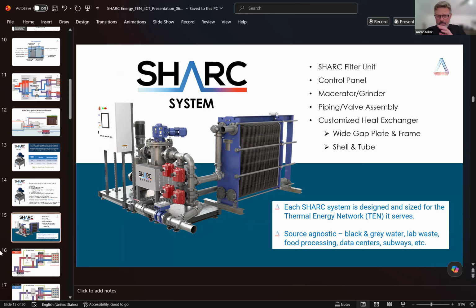Real quick, again, not to bore you, we've got a heat exchanger that we're trying to do like heat source, heat sink, and I've got a wastewater stream with some solids in it. So what we've designed is a very specialized front end which filters out those solids and a wide gap plate and frame or a shell and tube heat exchanger, depending on what you need, because we're very Canadian in that regard, very flexible. We're not only wastewater agnostic, but we're also heat exchanger agnostic.